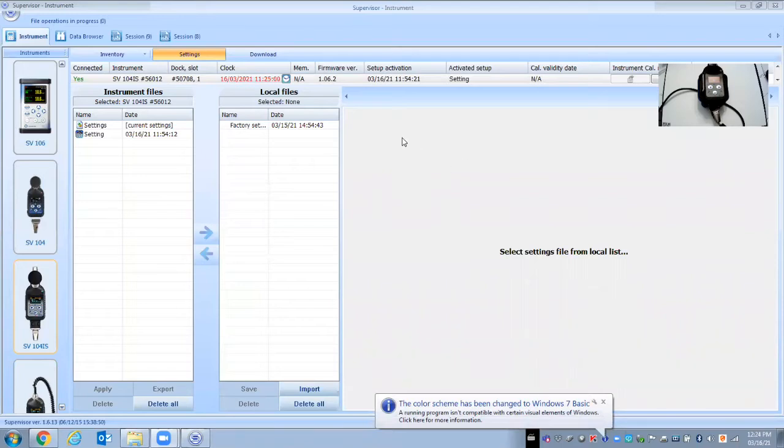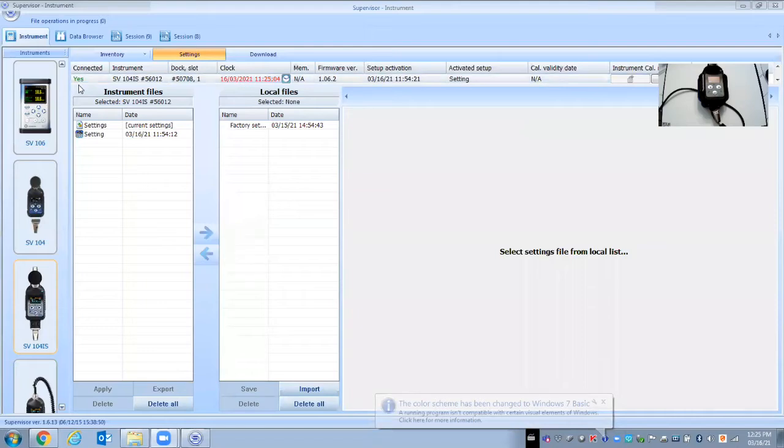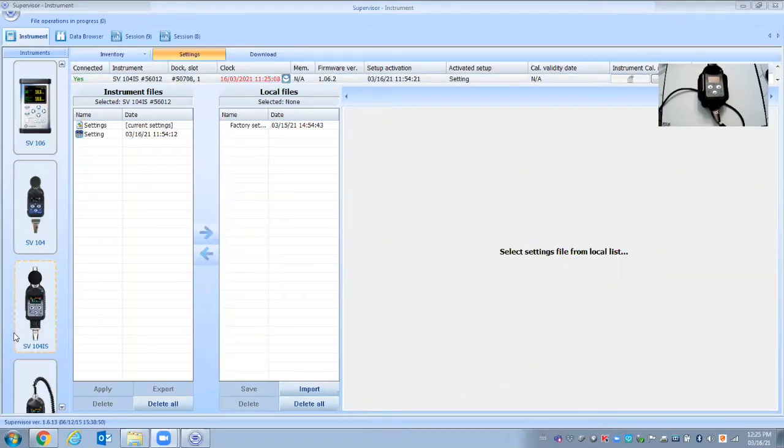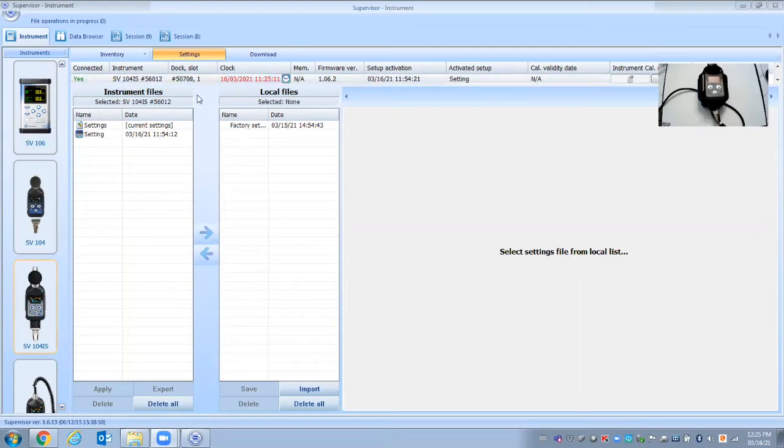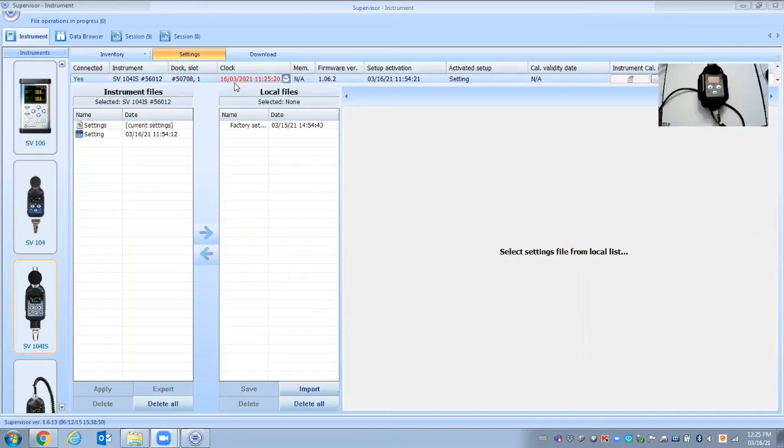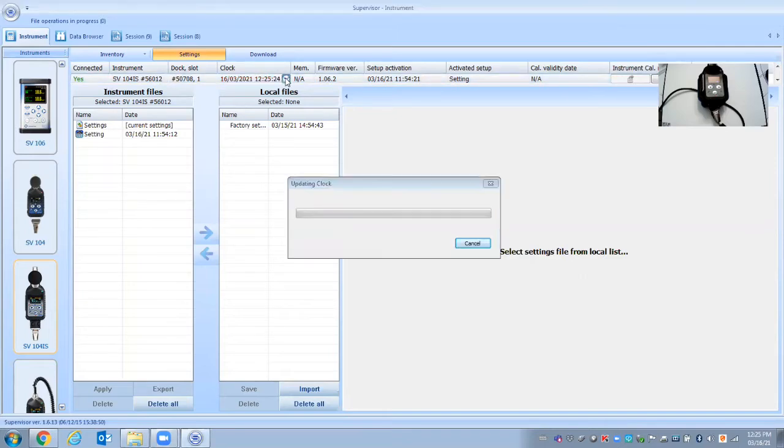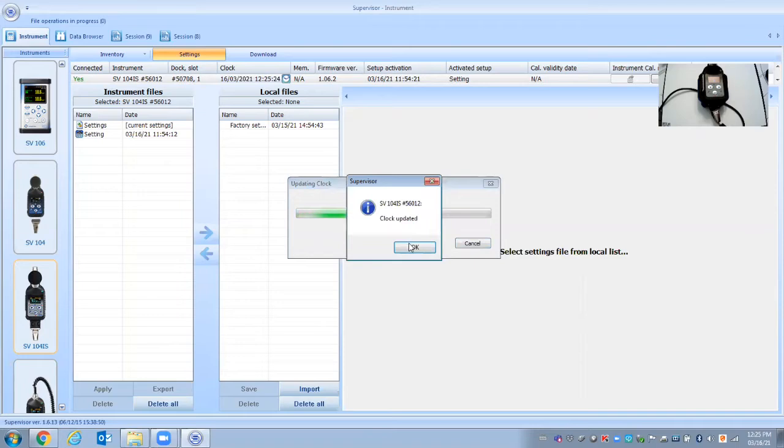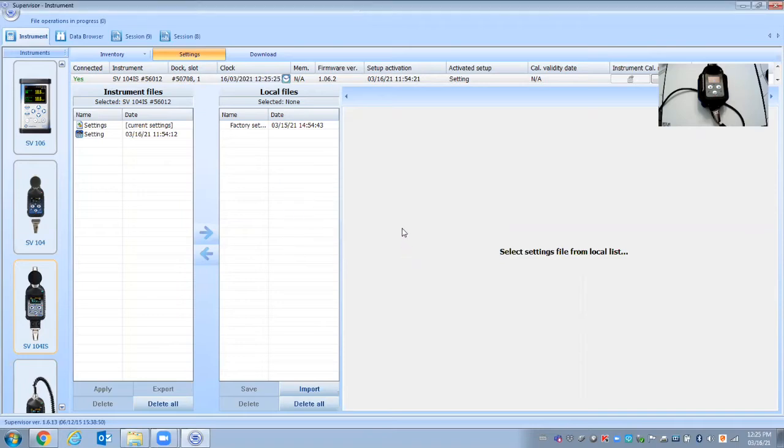So first thing you'd want to do is we can see up here that the software's recognized the noise dosimeter, says it's connected. In red here it's telling me that the time is not synchronized with the computer. So you want to make sure the time and the dosimeter and date are synchronized with your computer. So first you'd hit that. That's if it is showing red and not synchronized.